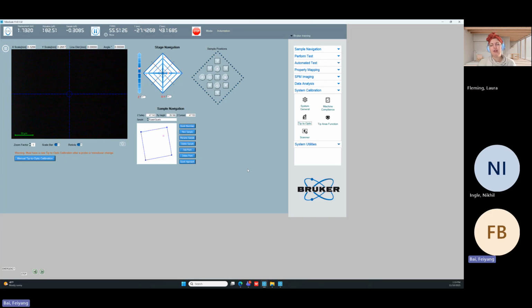You're looking for how that tip slides across the sample surface. The most common examples are coefficient of friction, where you have a really big probe that slides across the sample and you're looking at the friction between those two items. The other really big example is the critical point of delamination. That's where you try to have plastic deformation to dig into the sample, to wear away some of it so that you can see when you break through a coating or some other interface of some sort. So those are the two major ones.